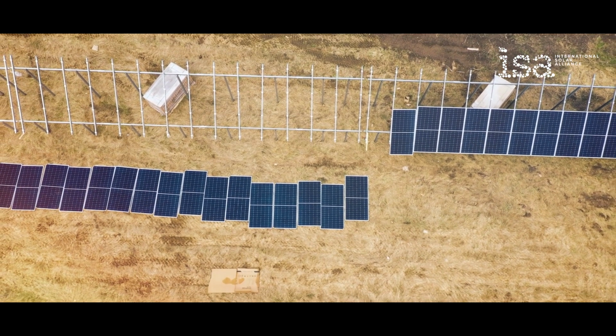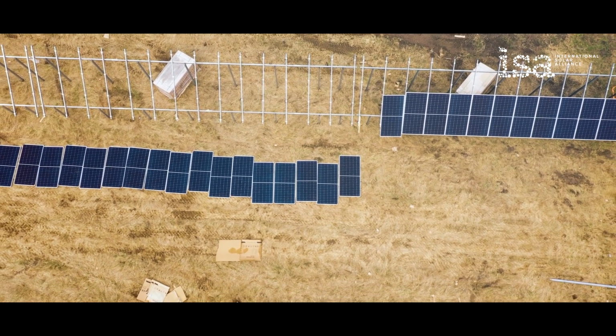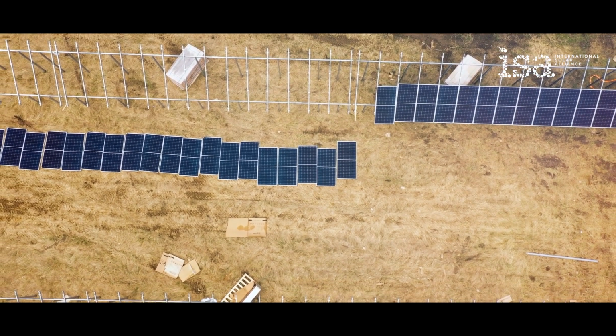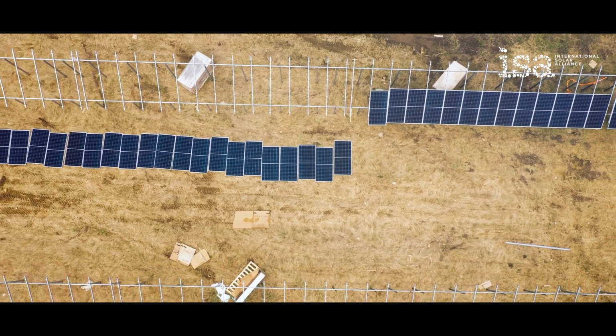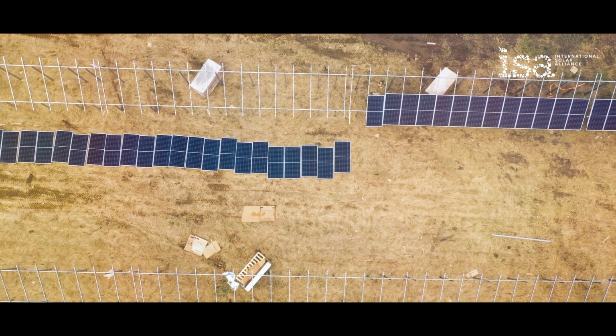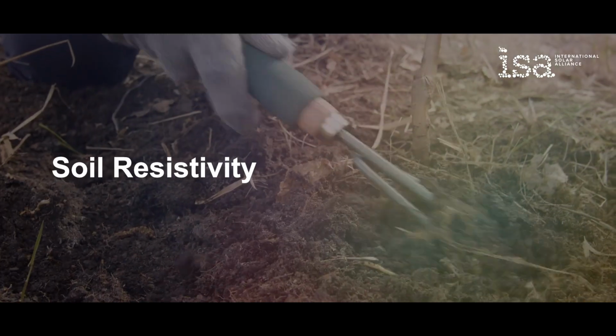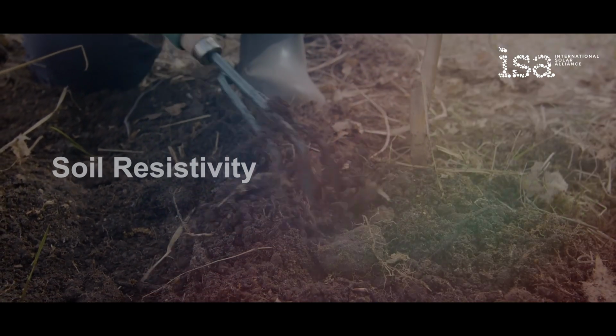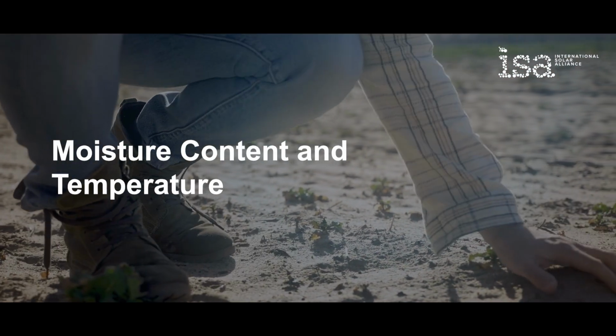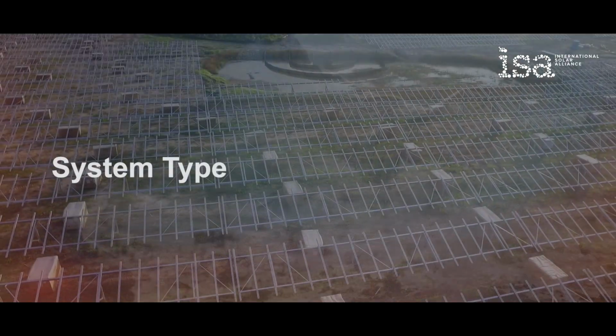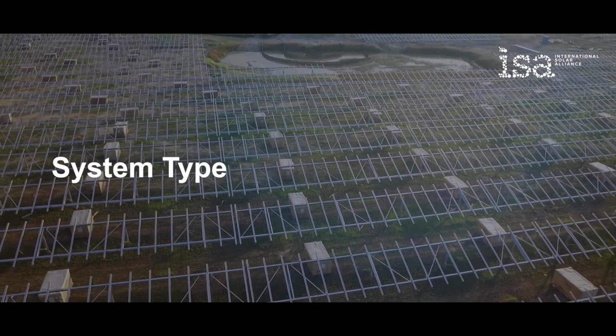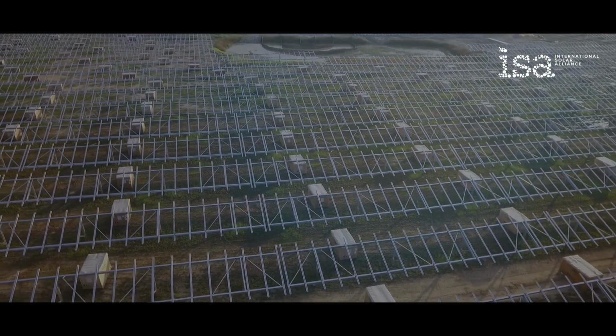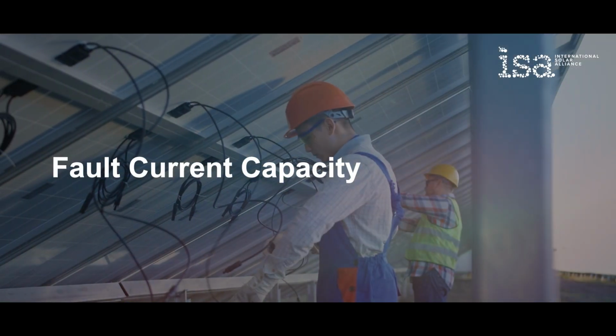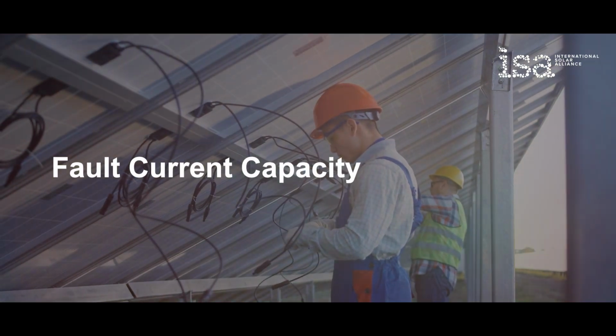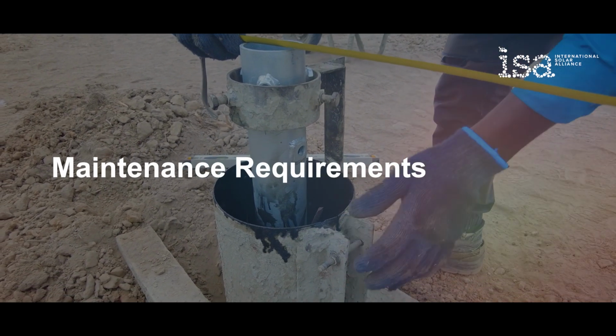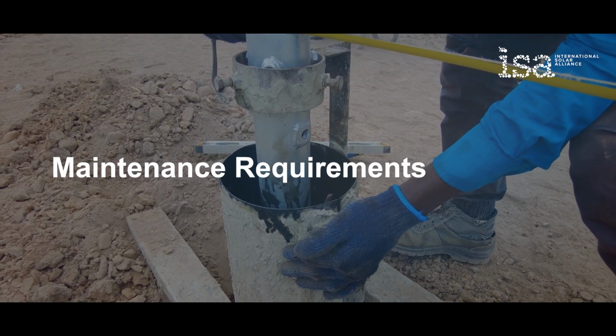Selecting the right earthing system in solar PV plants is vital to ensure electrical safety, protect equipment, and maintain consistent performance under varying environmental conditions. The selection depends on several key factors. Soil resistivity determines how easily electric current can flow through the ground. Moisture content and temperature affect the stability of earthing resistance over time. System type, whether grid-tied, off-grid, or hybrid, influences grounding configurations. Fault current capacity: larger systems require earthing arrangements that can safely dissipate high fault currents. Maintenance requirements: earthing pits must be accessible for periodic resistance testing and inspection.